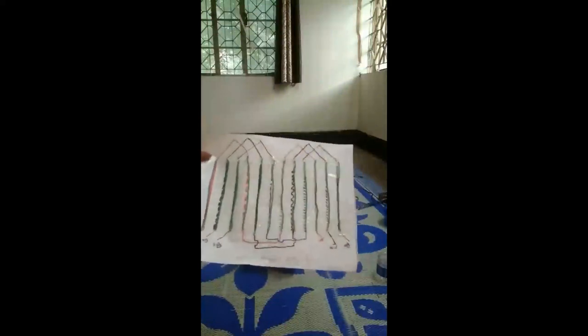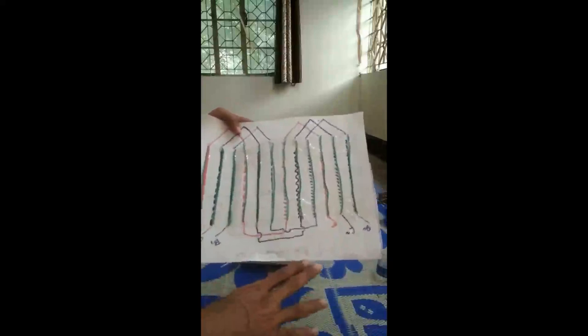Or stating it another way, for the first configuration, your current was just 1 ampere, suppose, and now when you connect the dissimilar ends, it has become 4 ampere. Why? Because you are connecting A1 at this dissimilar end, so they form a parallel path carrying current in the same direction, and similarly these two. When you connect all these four in parallel, you are allowing four times the current flow through this parallel combination. So in this way you can generate different star and delta windings for your need. This is only a very simple single layer, 12 slot, 3 phase, 4 pole machine.